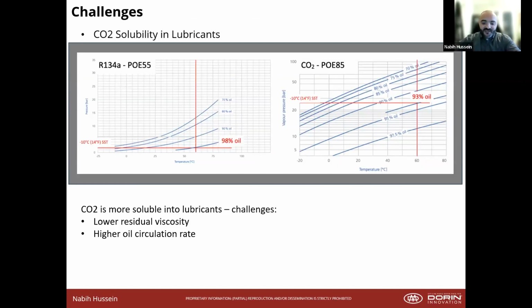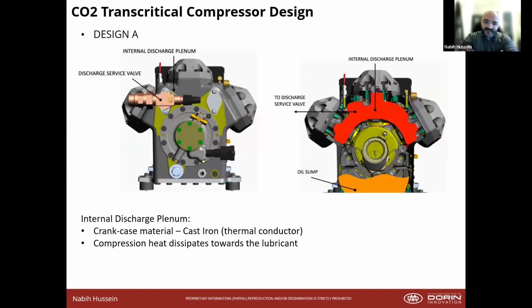As a designer, you want to make sure everything inside the compressor is lubricated. You have CO2 dissolving in your oil, and you're trying to deal with all these tribology issues. Here are two designs we have, because we do make semi-hermetic reciprocating compressors for HFCs and CO2. We had our internal discharge plenum design. This came with the problem that the internal discharge plenum gives heat to that oil, right? It's heating up that internal oil, and we have the constraint of keeping the oil cool, so the residual viscosity is higher.